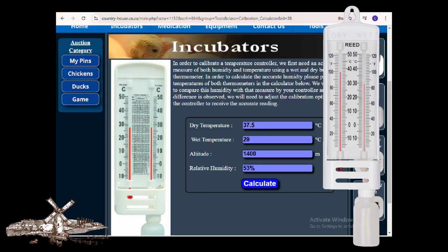Now, I wouldn't be too tied up with trying to get terribly accurate with the humidity. If my controller is measuring 55 and the real humidity is 53, that would be a suitable accuracy. I would be more than happy to put my eggs in the machine. So by doing this, we've now checked our incubator controller. We've identified that it was wrong, and we have now corrected the values.